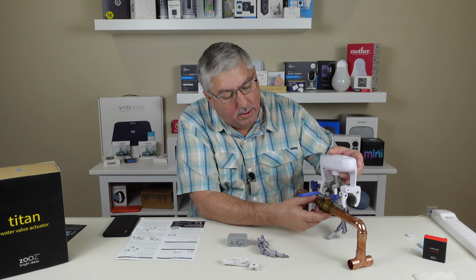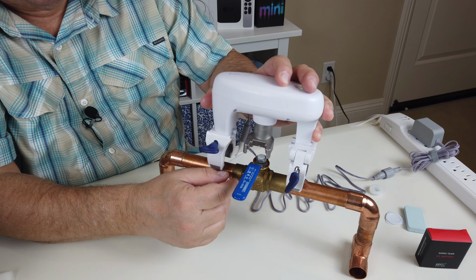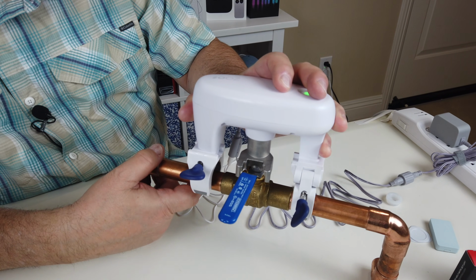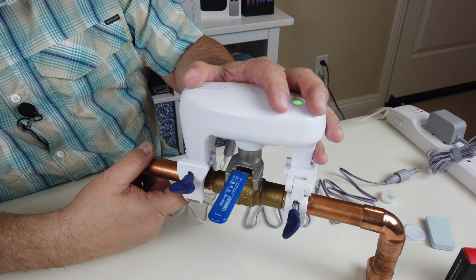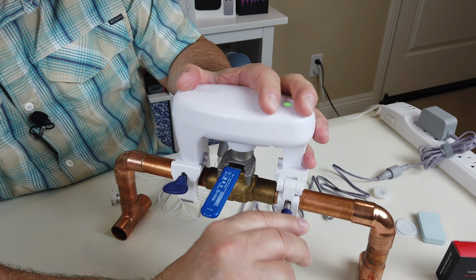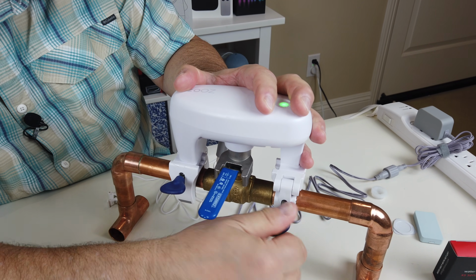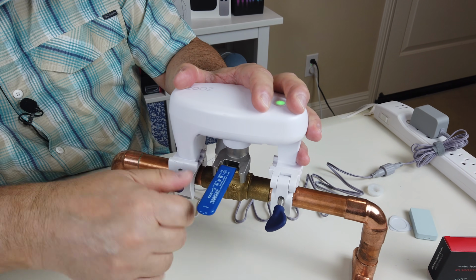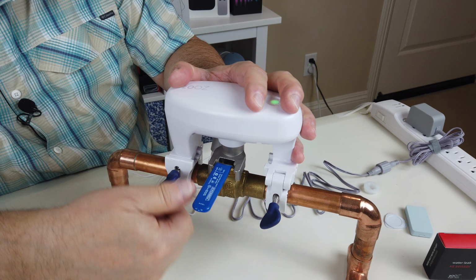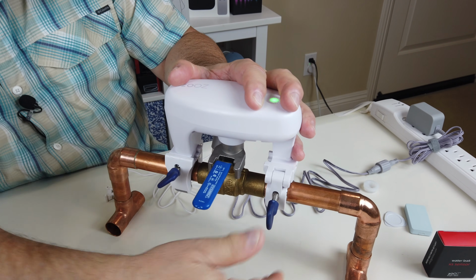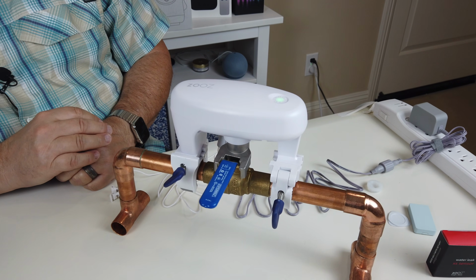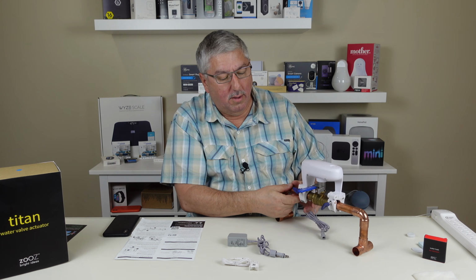Let's go ahead and do it again. We put it over the nut there, and see, it hits the valve, and then we push it down, and it's spring loaded. We just tighten these clamps, and that's it. We've now installed, at least mechanically, the valve actuator.